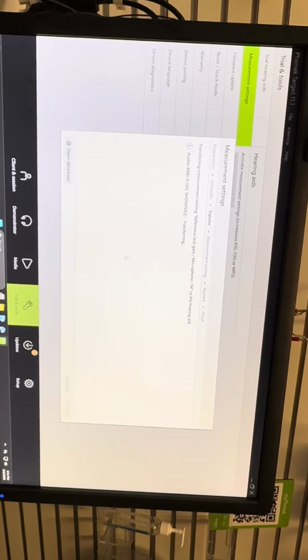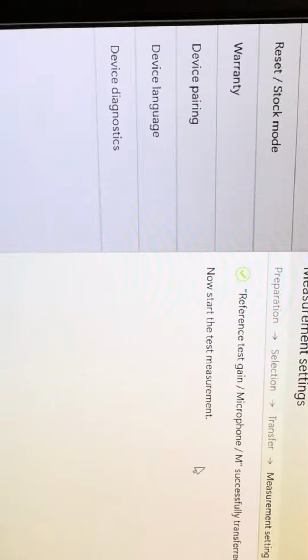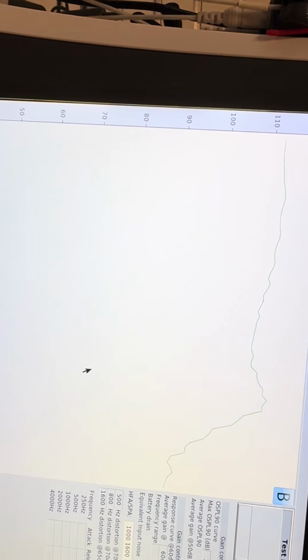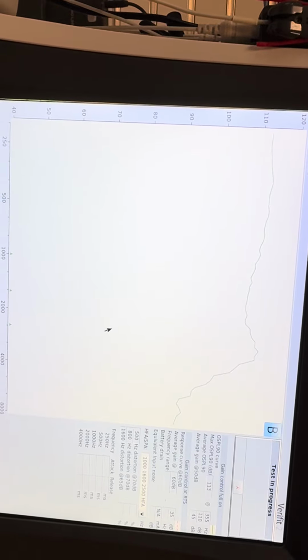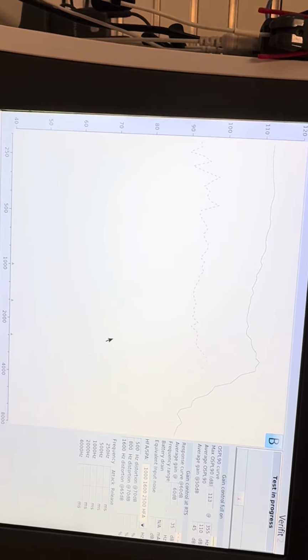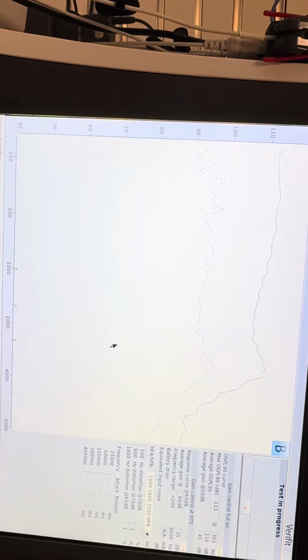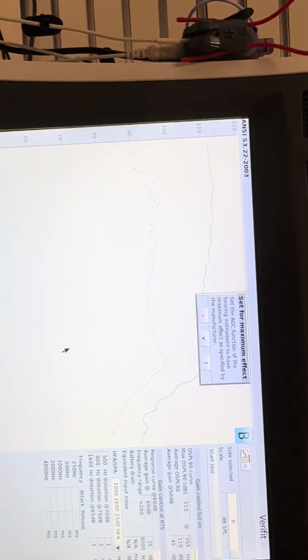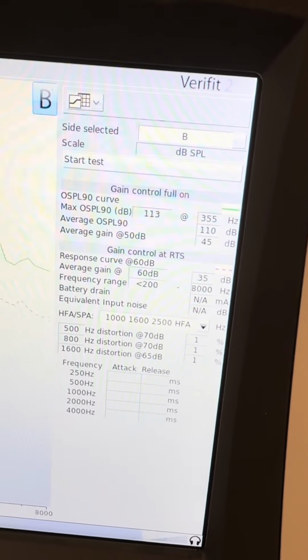Now we want it reference test gain M still. Just wait a little while. And here, you know, it's fully set when that triangle gets really tiny and it says we can start the measurement. So we hit continue. All right, now the test is complete. You have all your values that you need here to compare to the spec sheet.